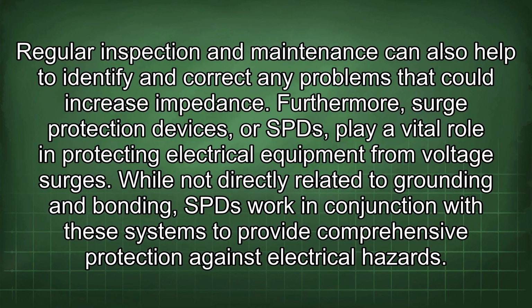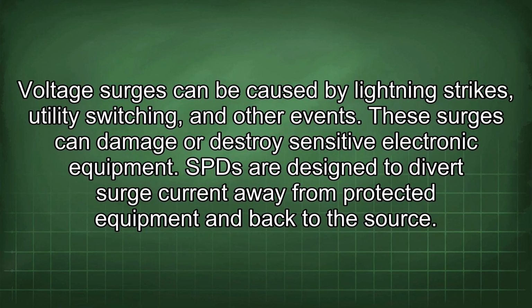Furthermore, surge protection devices, or SPDs, play a vital role in protecting electrical equipment from voltage surges. While not directly related to grounding and bonding, SPDs work in conjunction with these systems to provide comprehensive protection against electrical hazards. Voltage surges can be caused by lightning strikes, utility switching, and other events. These surges can damage or destroy sensitive electronic equipment. SPDs are designed to divert surge current away from protected equipment and back to the source.